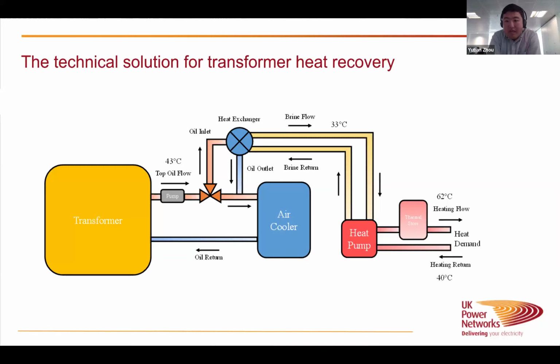This is generally being considered as the most effective solution for recovering and upgrading the waste heat from power transformers. Ideally, at the SGN Commercial Services Department within their energy center, thermal storage is also proposed, which will help with the electricity demand profile, the waste heat profile, and also the heat demand profile.